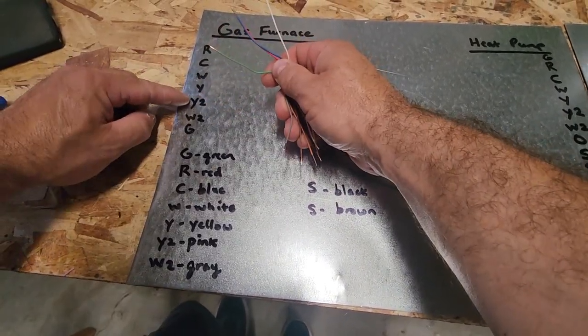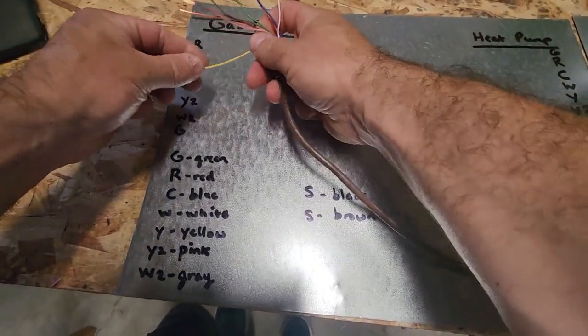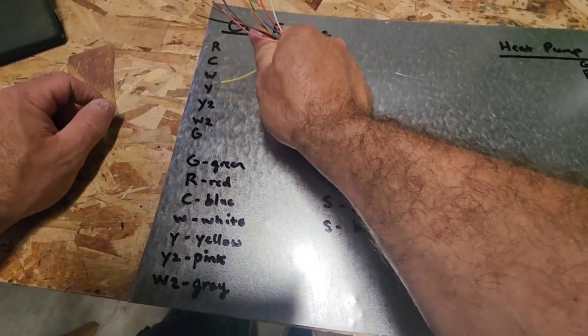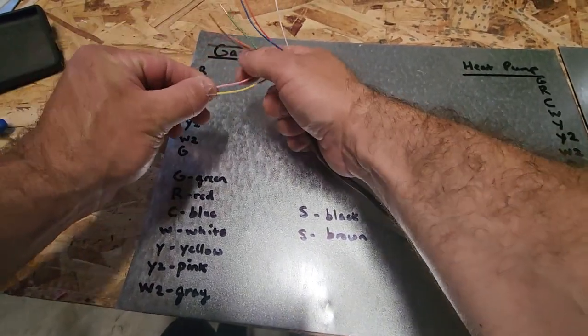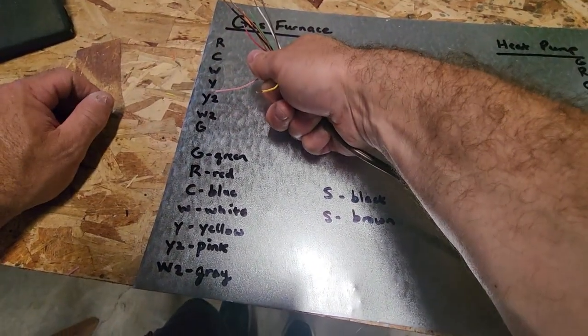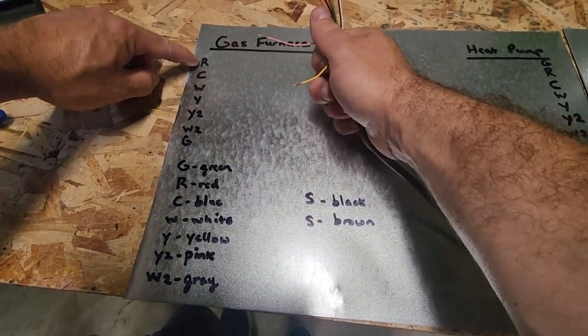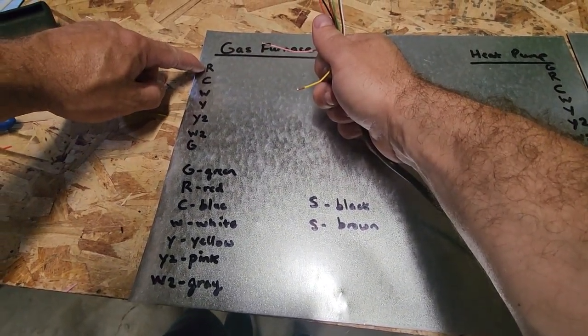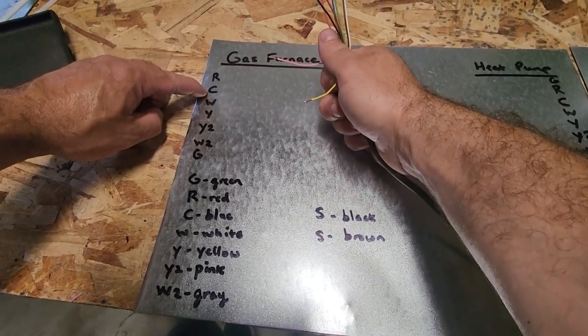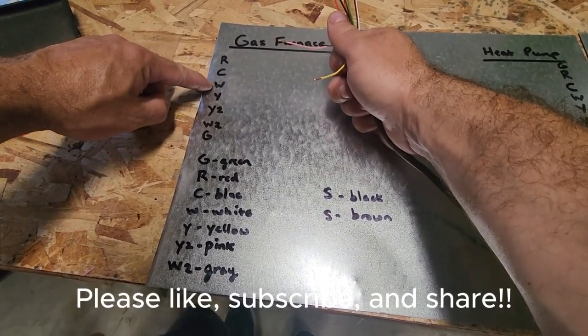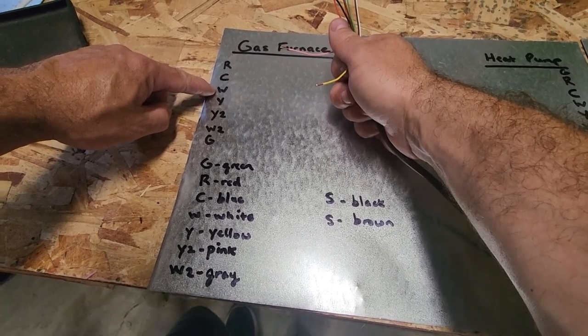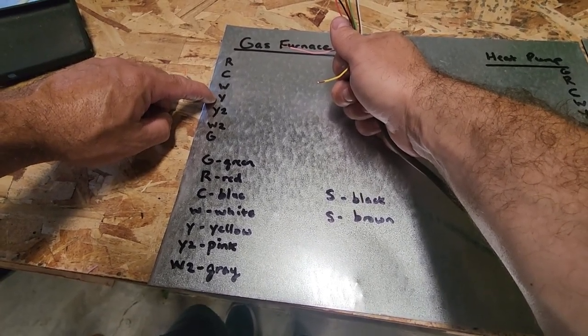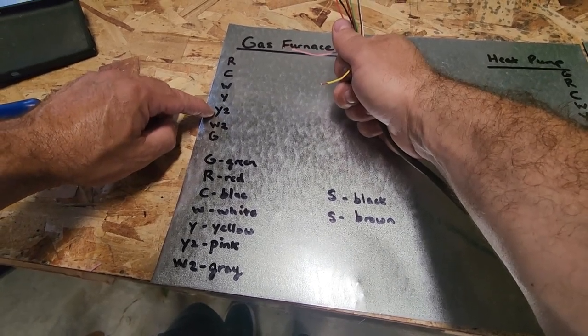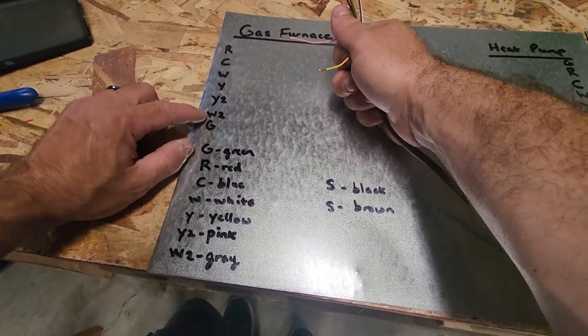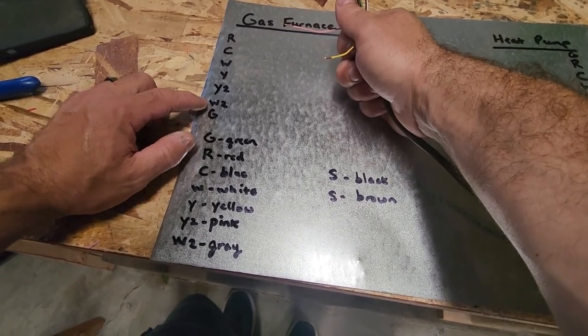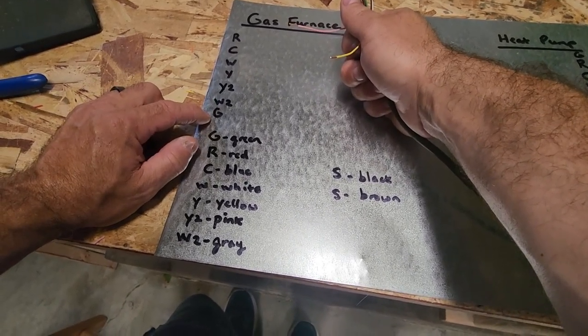If you have a second stage of cooling, well, let's do first stage first: first stage is always going to be yellow, always yellow every time, do not ever change. For my second stage cooling with my 10 wire, I like to use pink. So to recap: 24 volts hot is red, C is our 24 volts common, blue; W is white, that's our first stage heat; Y is yellow, that's our first stage cooling; Y2 I like to use pink, that's our second stage cooling; W2 is gray, that's our second stage heat; and G is fan, that's always green, okay?